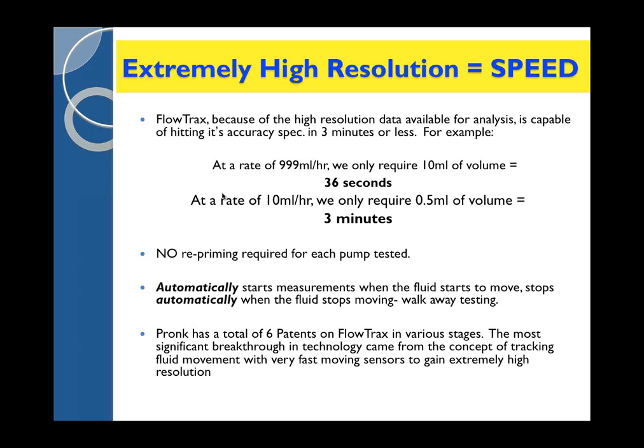What does that extremely high resolution mean? It equates to speed. For example, at 999 milliliters per hour, we only require 36 seconds and 10 milliliters of volume to hit our spec of 1% accuracy. At a rate of 10 milliliters per hour, a really low rate, we only require half a milliliter volume, which is equal to 3 minutes.